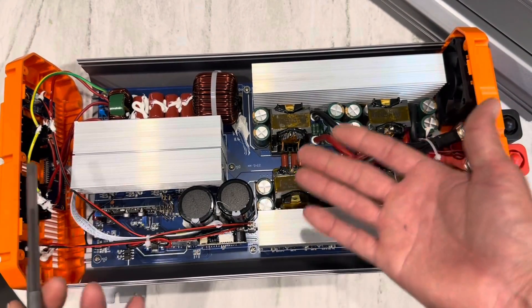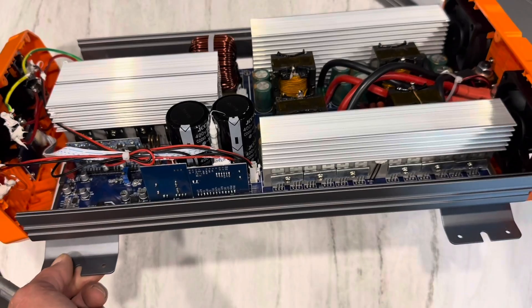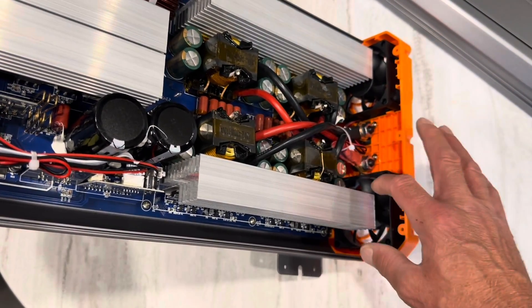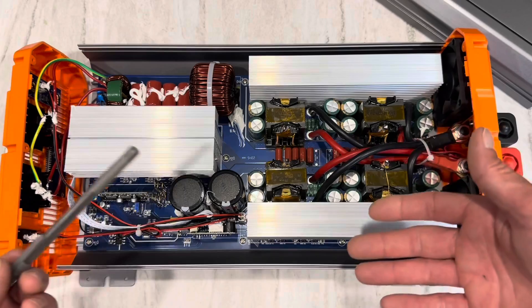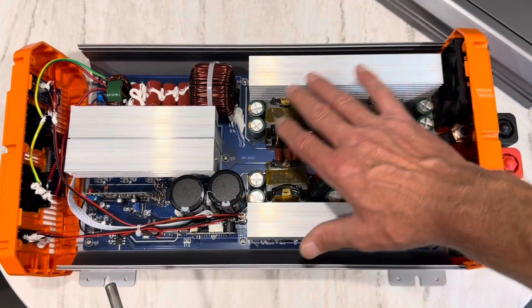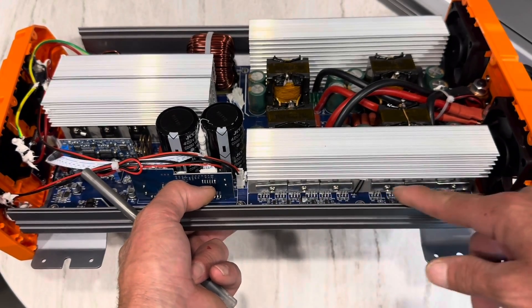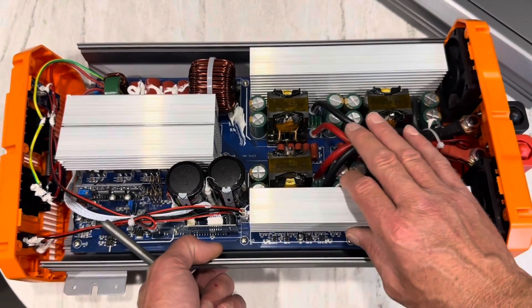On the AC output side, the wires are 180-degree Celsius silicone jacketed, 1.5 square millimeters, with large capacitors and large transformers — decent build quality. Considering the price, nothing really stands out as poor craftsmanship; it's well put together and right on par with other budget high-frequency inverters. The cooling fans have nice open airflow in line with the heat sinks. Notably, on this model the heat sinks are actually anchored into the PCB — not floating or relying on the FETs to hold them — which prevents the connections from fatiguing and means it can take vibration without anything shaking loose.